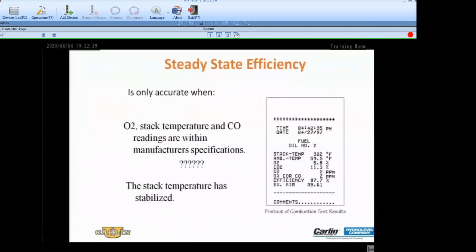Typical printout you might see when they have their results. And this is where we start to question technicians. How did you get to this number? Is that number correct? What should your stack temperature be on that appliance? You've done these tests more than me, more than the average guy. You know what this appliance produces. If it's supposed to be 450 and you're seeing 300, why? If you're supposed to see 450 and you're seeing 580, again, why? What is happening? What are these numbers and why are they changing?